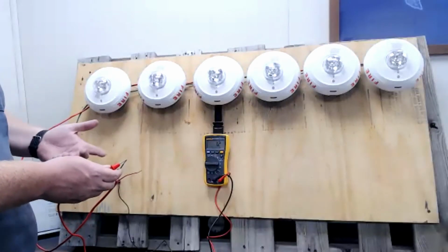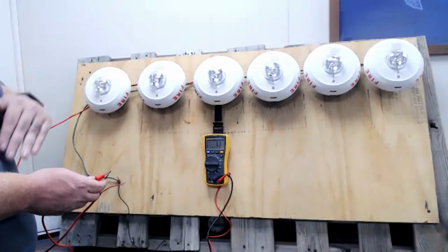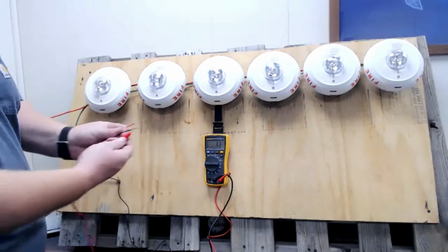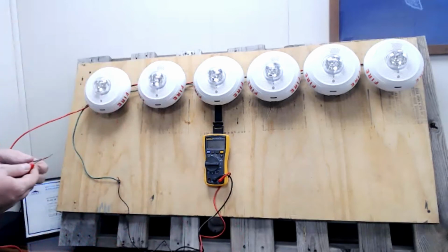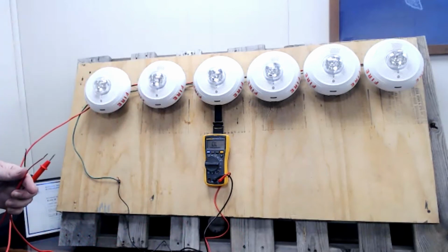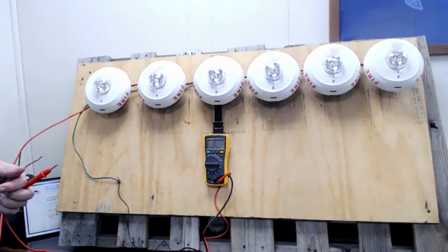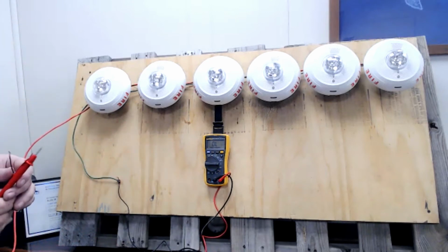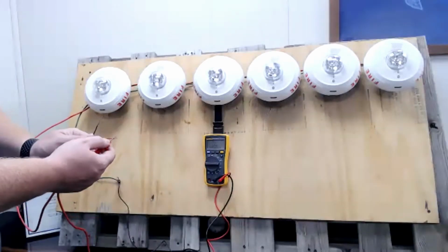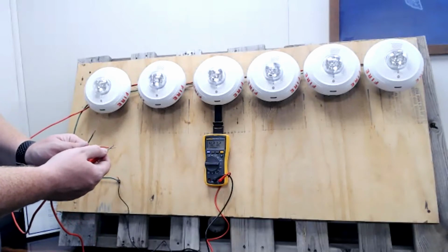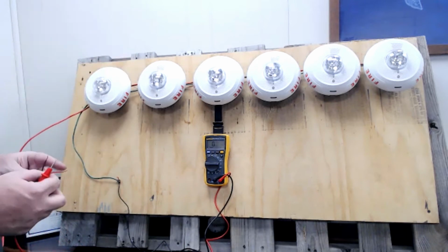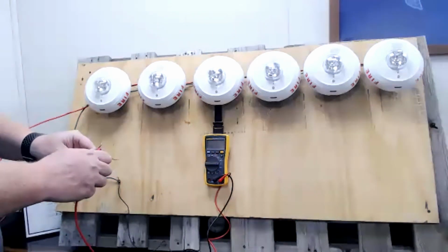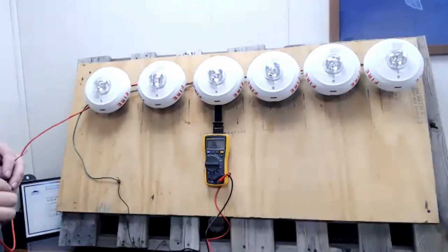So that confirms what I was thinking, that there was a ground fault on the negative side of the circuit, and it was seeing it by going all the way through the circuit. It's important to understand that the closer you are to a ground fault, the smaller the number you have, the less resistance you'll have. By connecting to the red conductor, the positive conductor of the circuit, it's further away than the negative conductor because it has to go all the way through the circuit to circle back to it. Whereas the ground fault is on the negative, so just by tracing the wire, I'm already a lot closer.